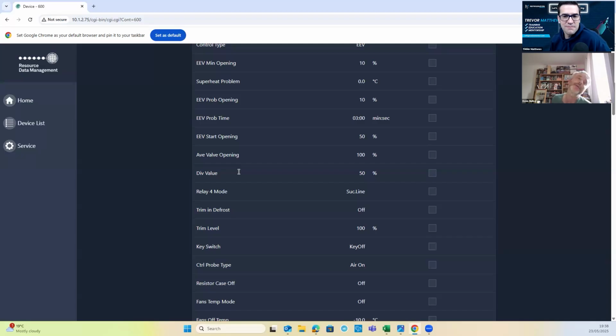And it's going to do that until the controller senses that the pressure has dropped by the MOP differential. And then it's not going to put the valve straight back to where it was. It's going to let the valve start controlling again. And it's going to keep doing that until it sorts its pressure out. So it's load control. RDM has many other ways as well of doing shutdown, but that's your primary load control, if you like, through your controller.